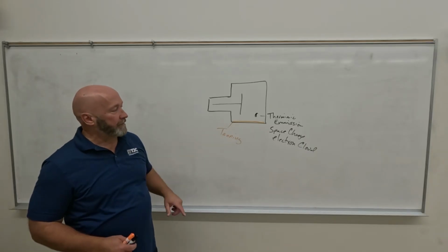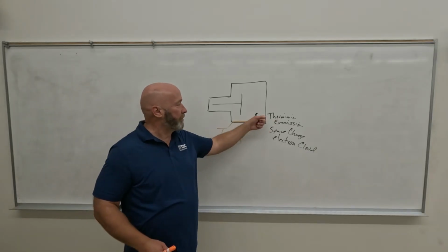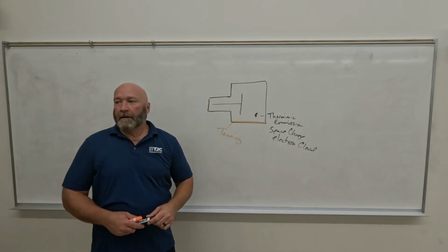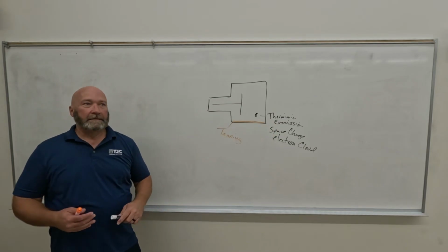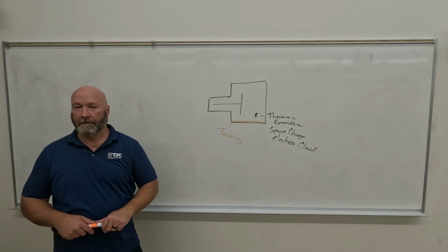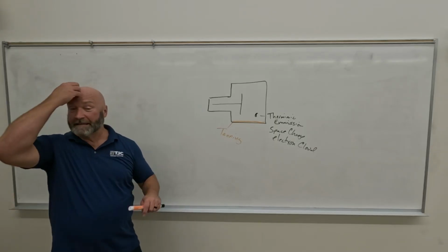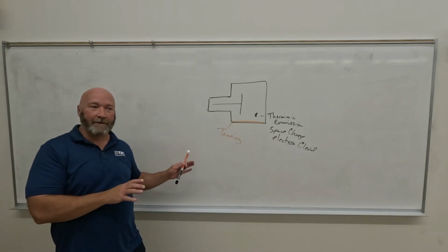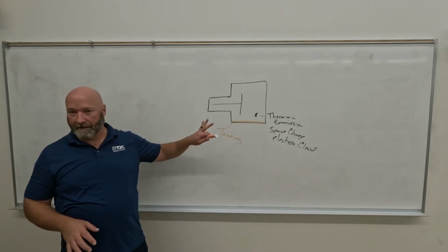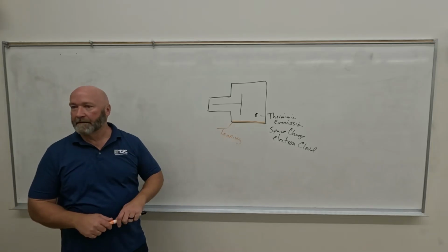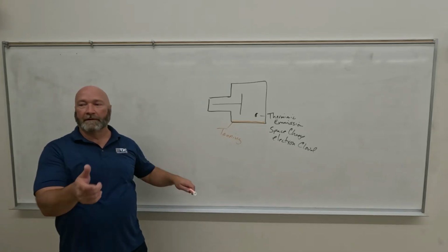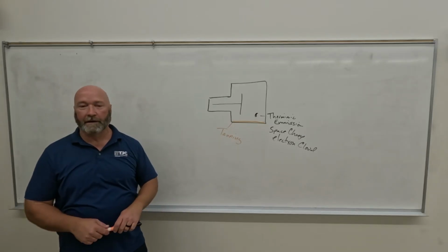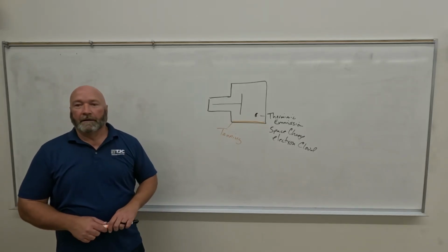Okay, I'll get there in a minute. So we've got two different things going on. One is eventually we're going to burn it out, and two is that we're going to tan the tube. So how do we make X-rays more safe? I want you to know this, but this is not really for this test. This is an explanation of why we do the things that we do to try to keep the tube cool. We fail, but we try.